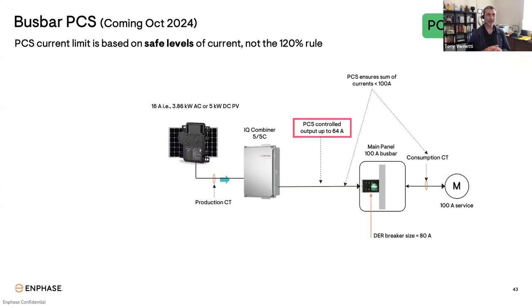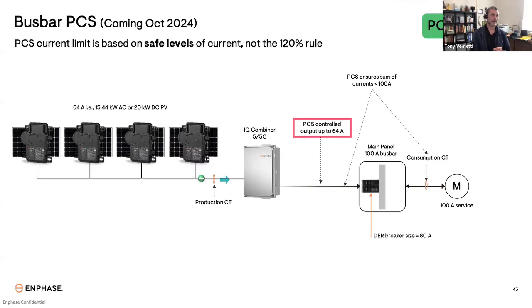And in this example, we have a 100 amp main panel again. The 120% rule says the max backfeed breaker is 20 amps, which again is 16 amps continuous current, and only about a 5 kilowatt PV system, smaller than what most people need. So Busbar PCS uses measurements of electrical current from the PV system and from the grid with consumption CTs, and will allow as much as 64 amps of backfeed current from the PV system. Now, 64 amps is a very large PV system of around 20 kilowatts DC.